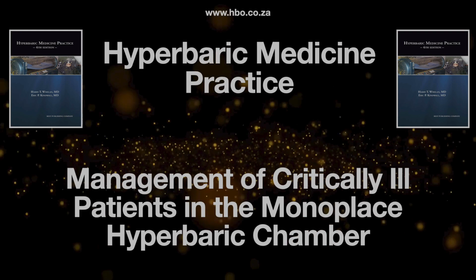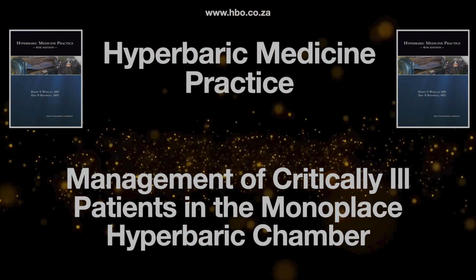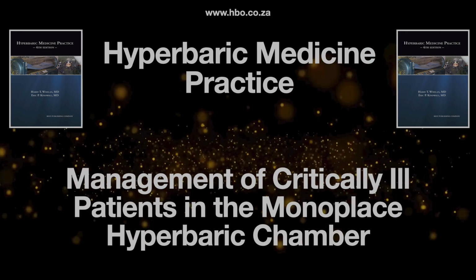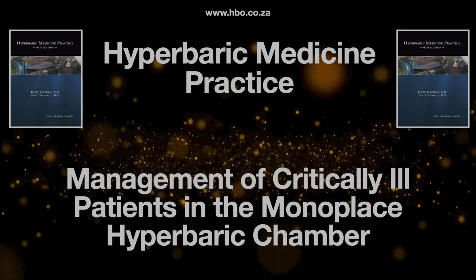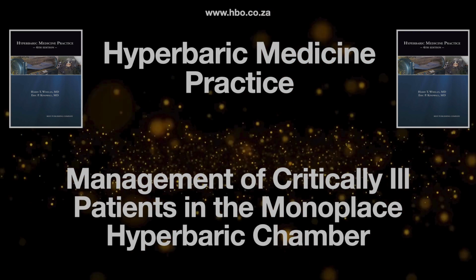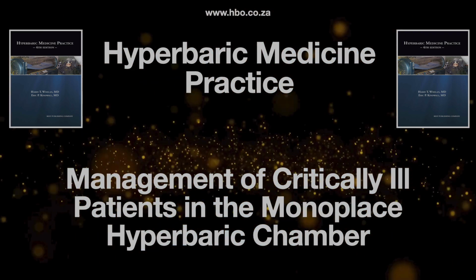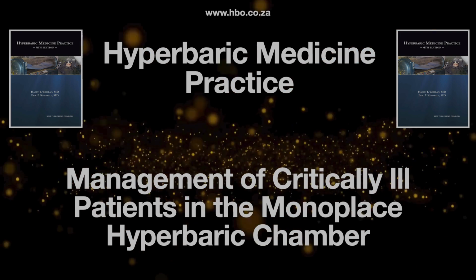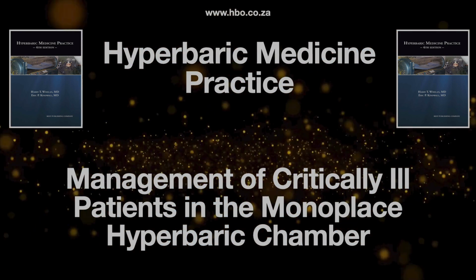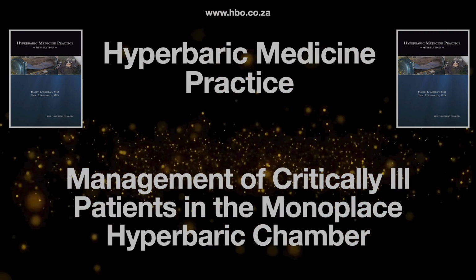And the ventilator itself, the Sechrist 500A, is common, right? How does that work with oxygen? Yeah, the 500A is pretty standard. It actually pulls in the gas around it to give the breath. So if the chamber is filled with 100% oxygen, that's what it uses. But if the patient needs a really high FiO2, you might need to bleed supplemental oxygen in right at the ventilator's intake valve inside the chamber. Okay. And pulse oximetry is key throughout. Constant pulse oximetry, yes, absolutely essential.